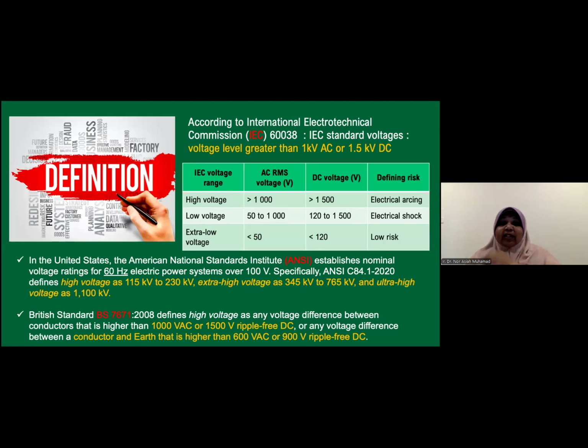Before we go further, let us know what high voltage is, what we can consider as high voltage. For electrical, we are bound by standards, so all our work and testing are based on the standard. There are a few standards around the world. The most used in Asia are the IEC standard or the American standard. Malaysia has its own Malaysian standard, while Brunei adopts the IEC standard. For the IEC standard, high voltage is defined as voltage greater than 1 kilovolt for AC, while for DC, 1.5 kilovolt and above is defined as a high voltage network.